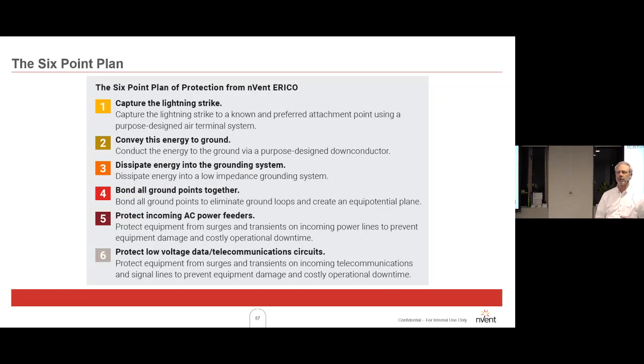If you need to have enhancement there, ideally you'd do a soil resistivity survey where you'd measure the resistivity and determine if you're going to use horizontal conductors in the ground, or you might need to use deep driven. If you're in a high pedestrian area, you may want to use the deep driven electrodes and put insulation at the top so it doesn't have earth potential rise where the pedestrians are. You need to bond all your points together, and you need to do it not daisy chain, because you end up with lightning currents going through different devices. You've got to go all to a common bonding point. Then you consider protecting your incoming AC, and then you look at protecting your low voltage data and telecommunications. So if you cover all those points, you should be properly protected.